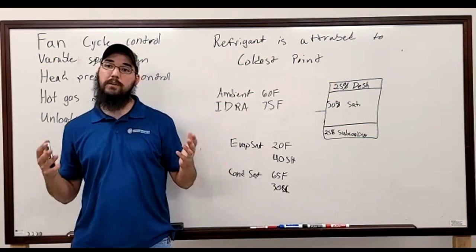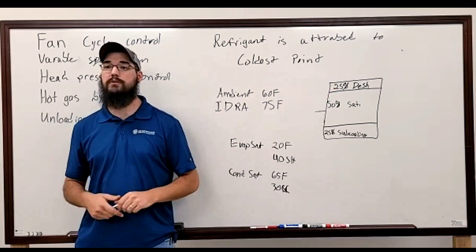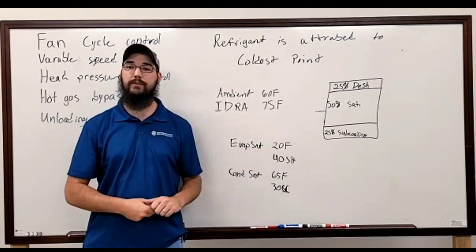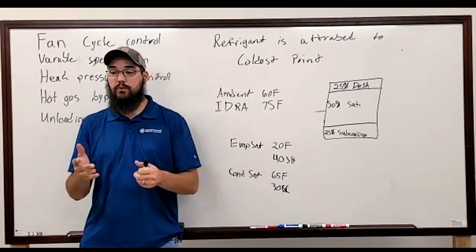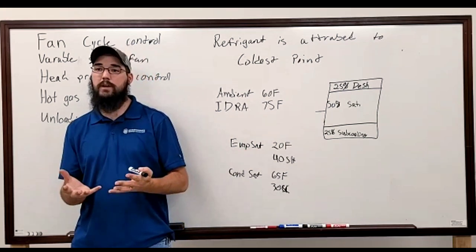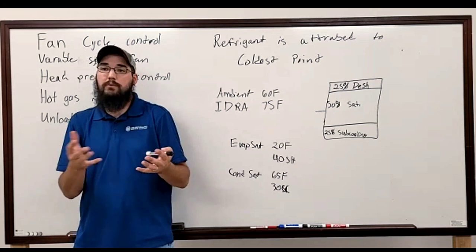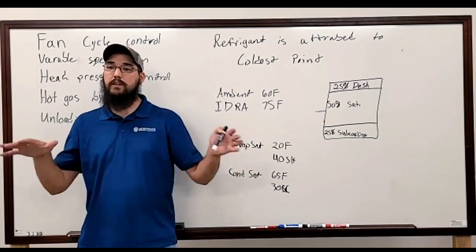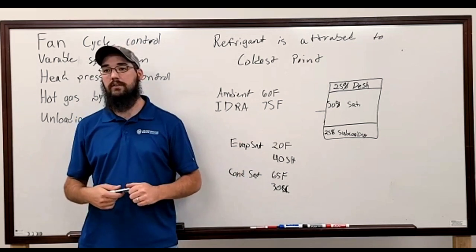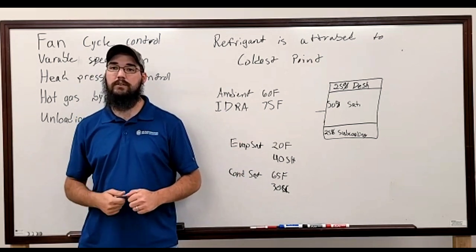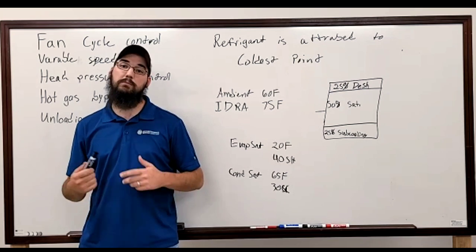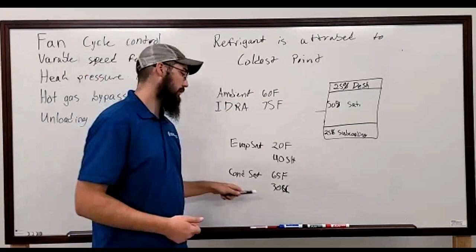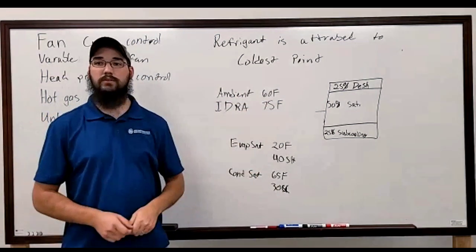Yep. And this becomes more and more common with microchannel systems, right? So that particular one we put in had a microchannel condenser. And you have so much surface area on those microchannel coils, when you get low ambient, they don't need a fan. They're able to completely reject all their heat without it, and they'll never notice. So we have to be mindful of those conditions, these states. This is real scenarios.